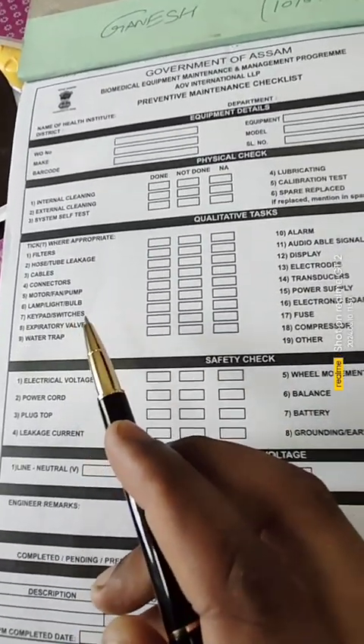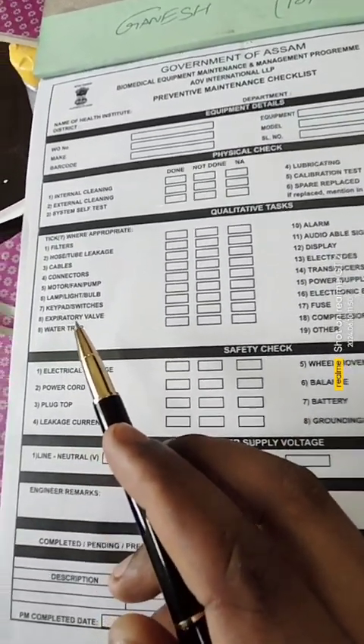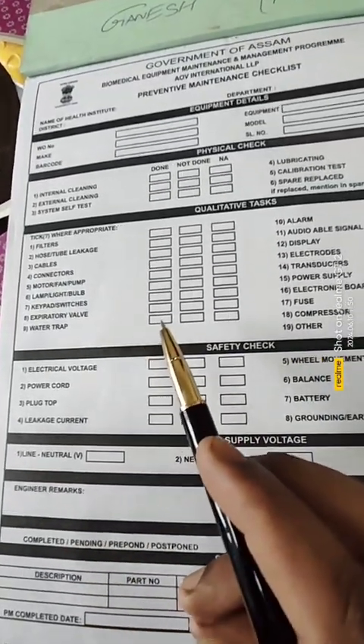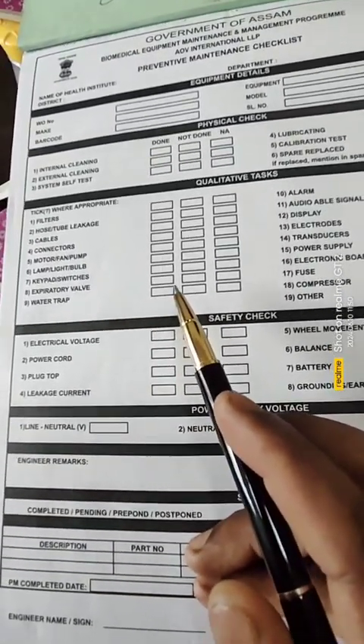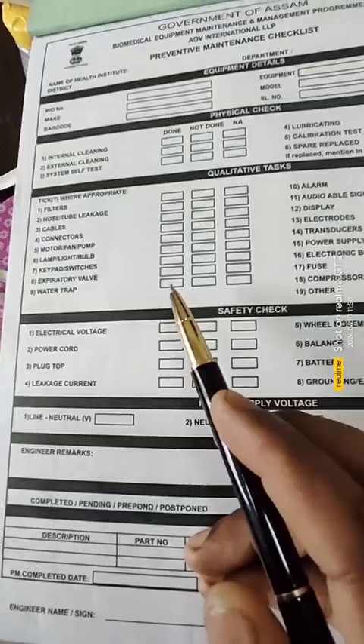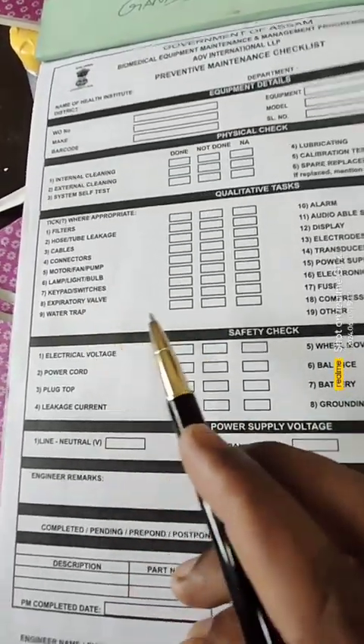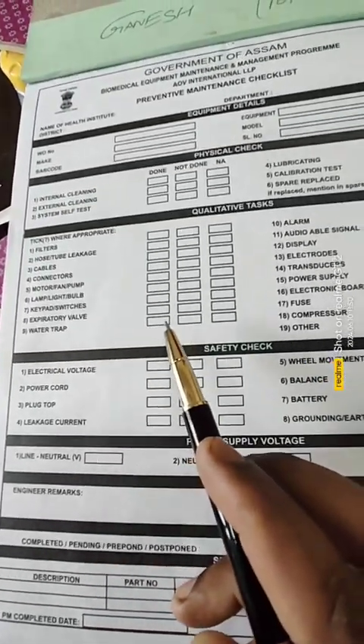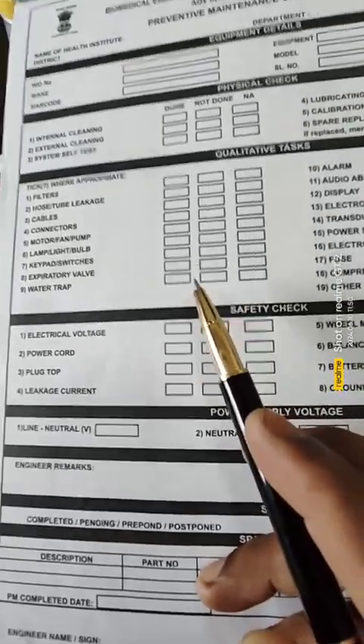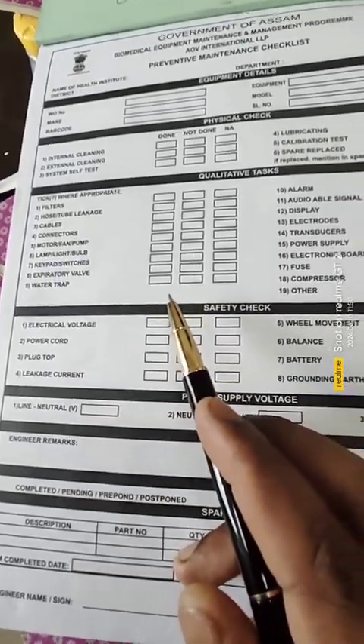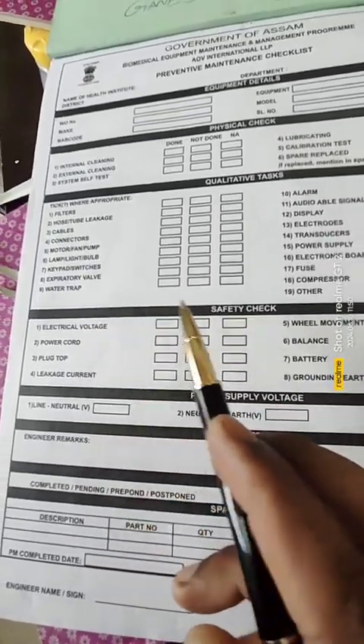Okay, lamp, lights, bulbs. Because we are observing the patient monitor, the light blinking and all things we can see here in front of the panel. So those are right or not. Keypad, switches, expiratory valve available or not: not available in the patient monitor. Yes, these are available in the ventilator. Okay, water trap, not available.